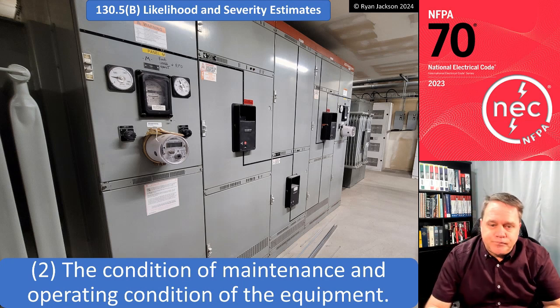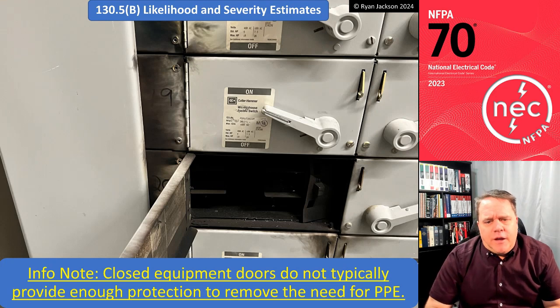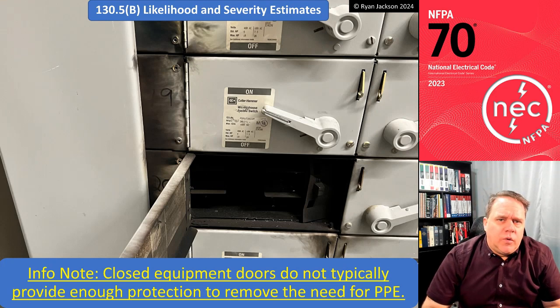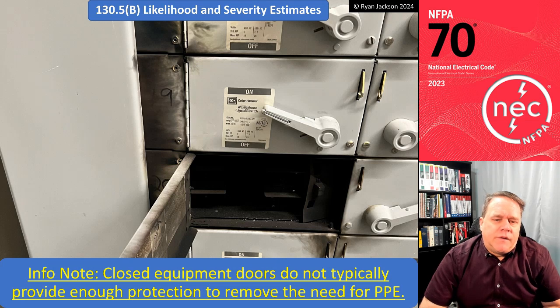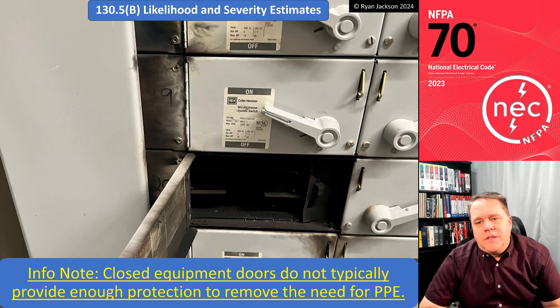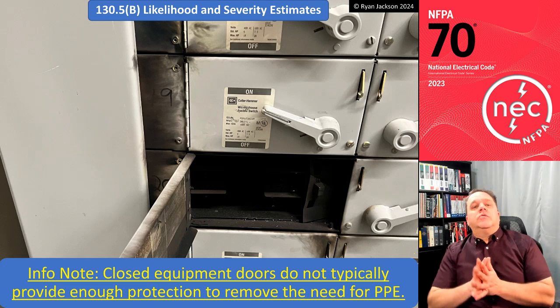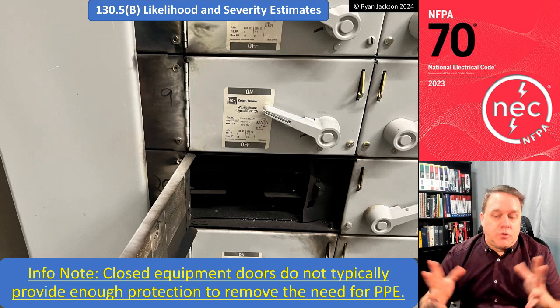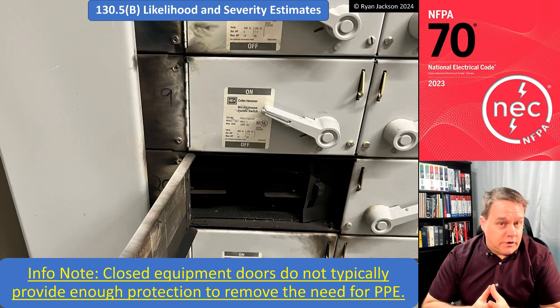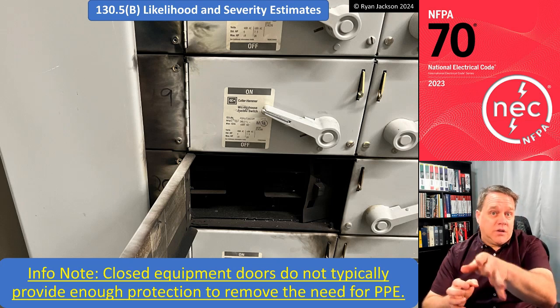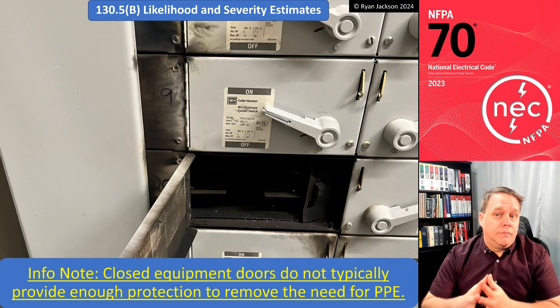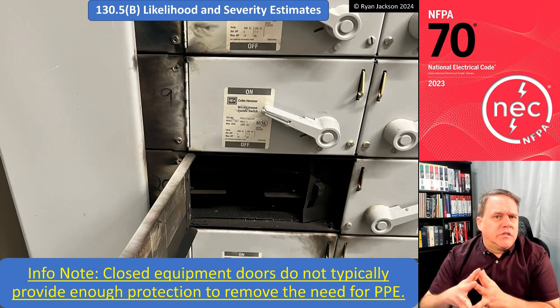There you have it. We added an informational note that says closed equipment doors do not typically provide enough protection to remove the need for PPE. Okay, closed equipment doors could certainly remove the risk of electric shock, right? If I can't touch the bare conductor or bare component, well then, yeah, there is no shock risk. Does that remove the risk of arc flash?